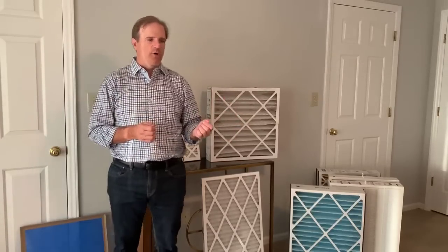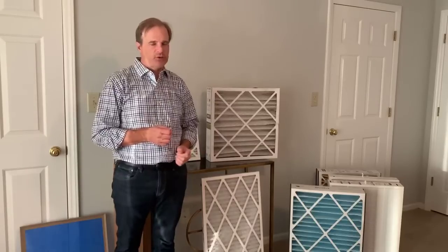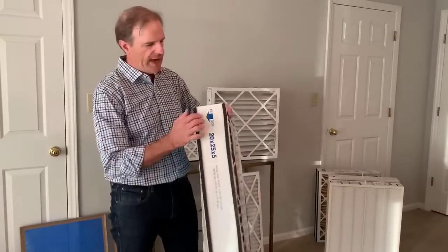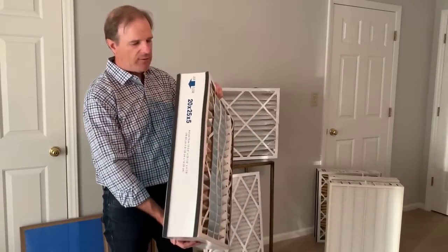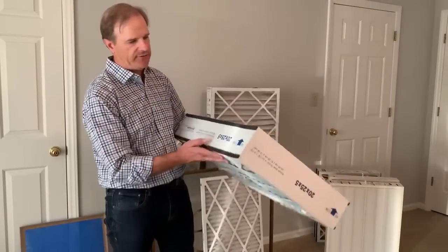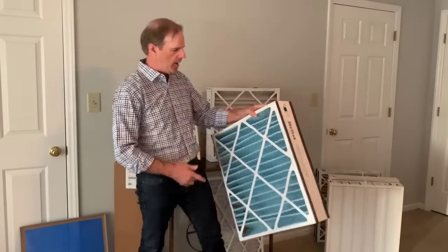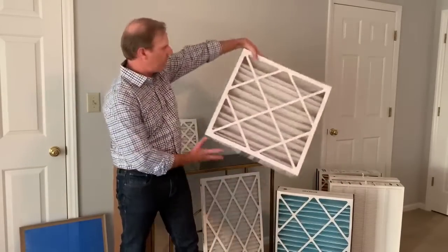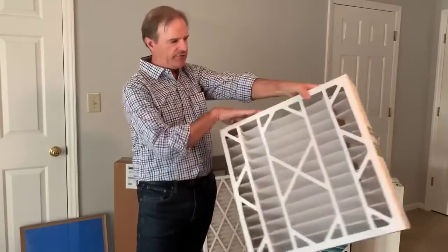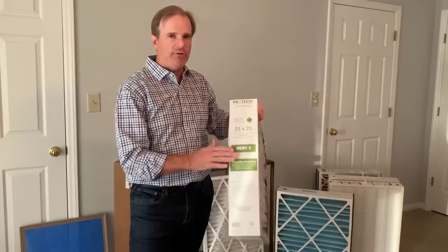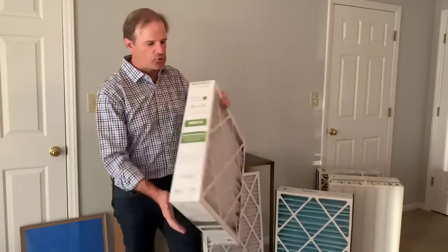So one of the things you want to do is make sure that your filter doesn't have any special characteristics. So when I say special characteristics, I'm talking about something like this filter has foam gaskets on the side of it. Now this isn't compatible for Air Bear because Air Bear has foam gaskets on both sides of the filter. So it's specifically made to be compatible for Air Bear. So that's one of the things you want to look for. If your filter, say, is just basically a box and doesn't have anything special and it's MERV 8 to 11, you can probably replace it with any compatible as long as it's the same actual size.